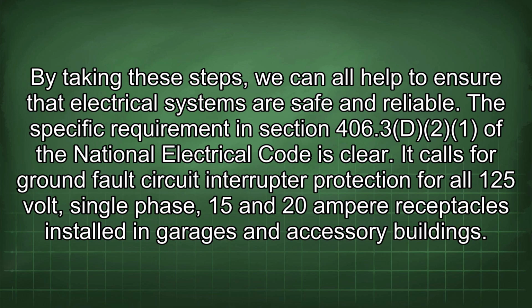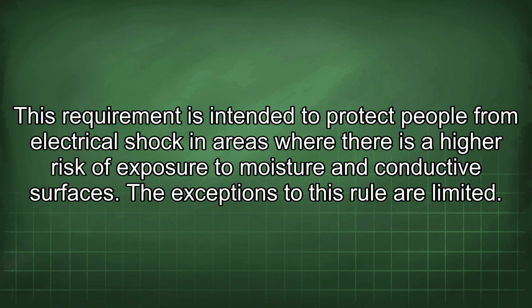The specific requirement in Section 406.3(D)(2) of the National Electrical Code is clear. It calls for ground fault circuit interrupter protection for all 125-volt, single-phase, 15 and 20 ampere receptacles installed in garages and accessory buildings. This requirement is intended to protect people from electrical shock in areas where there is a higher risk of exposure to moisture and conductive surfaces.